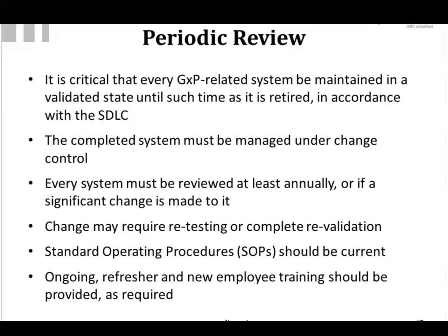Most changes will require some retesting, but some will require complete revalidation, particularly if you're going to interface your system to another system or if you're going to make major changes to coding. Your standard operating procedures should also be kept current. So if you have SOPs related to anything that you're going to reference during computer system validation and testing, you want to make sure there's a current version of that SOP available.